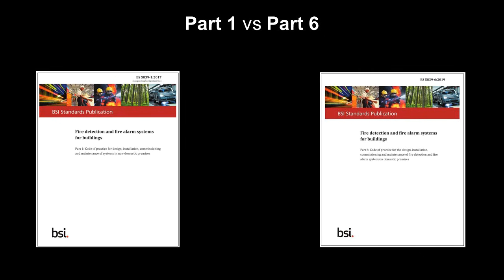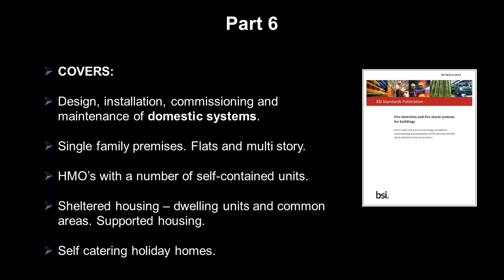And bear in mind, I hate using this word, but the standards are a guide, but providing you have sufficient knowledge and competence to design a system outside of the standards, and you have reasons to justify and mitigate some of the points raised, I think that's fine. But generally speaking, I think we should stick to the British standards. So Part 1 versus Part 6. Now, Part 1 of BS 5839 is commercial, which we'll go through in a second actually. And Part 6 is dwellings, it's domestic situations.